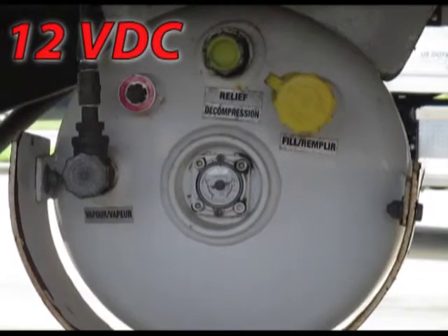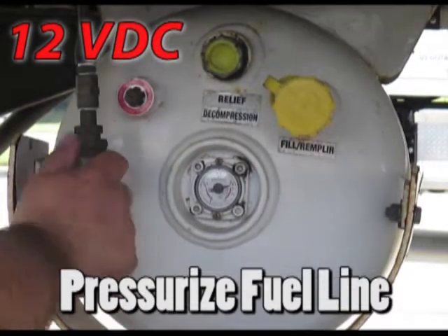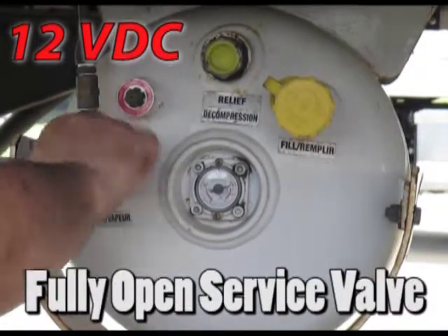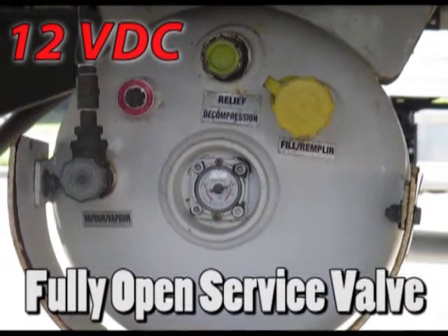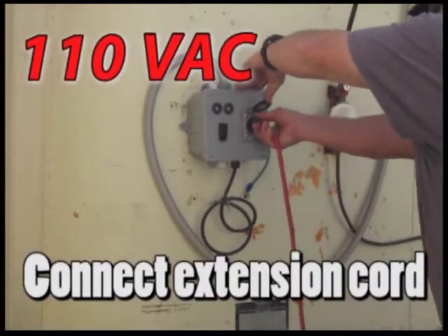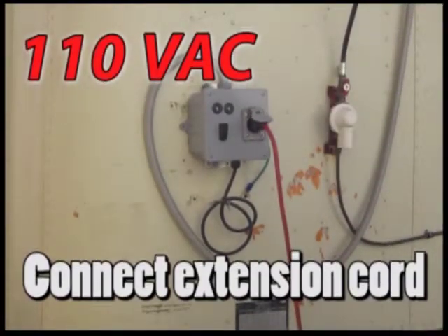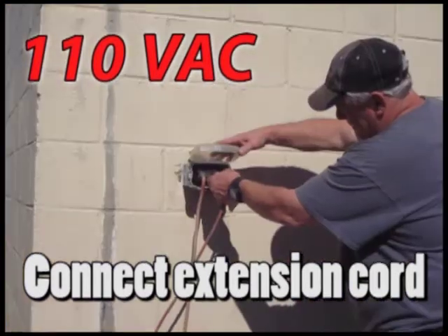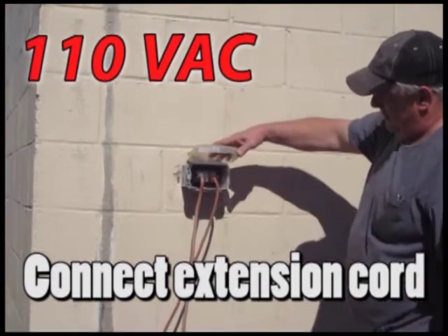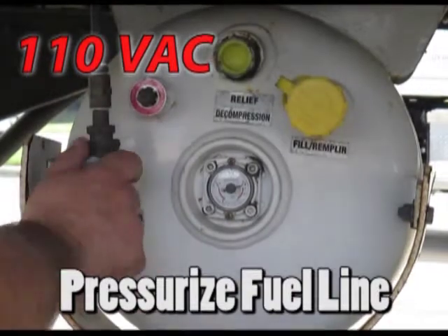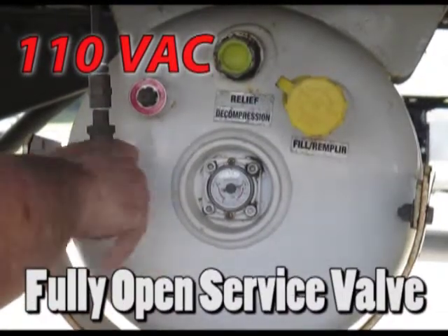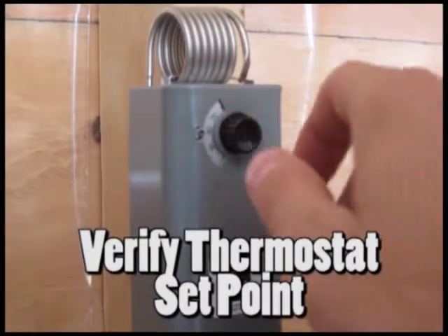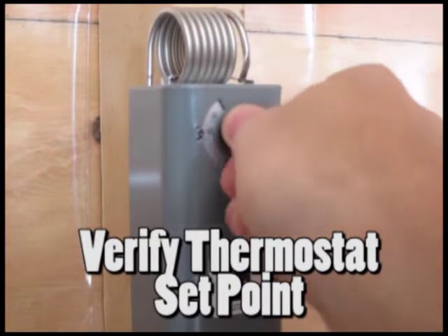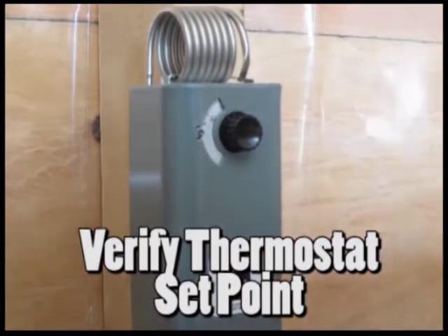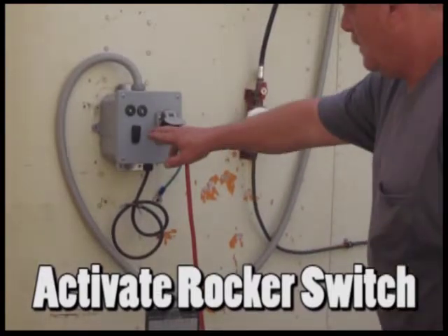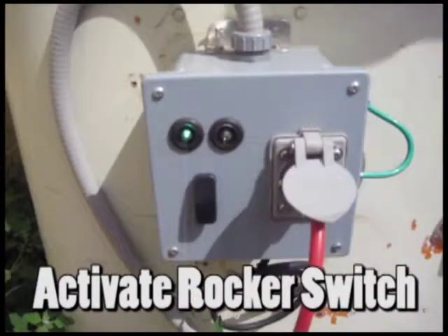While operating the heater on 12 volts DC, pressurize the fuel line by fully opening the propane tank service valve. While operating the unit on 110 volts AC, connect the extension cord to both the unit and the 110 volt power supply. Then pressurize the fuel line by opening the propane service valve. Next, verify the thermostat is set to the desired temperature for the trailer or truck body. Initiate the combustion process by activating the rocker switch on the control box.